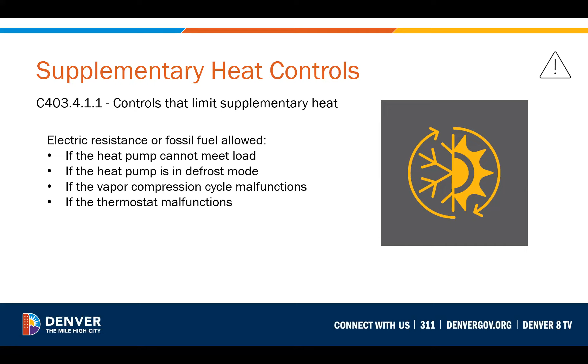Note that there is this supplementary heat controls requirement as well. The point of this requirement is just really to ensure that the heat pump is being used as the primary source of heating in a heat pump system, and that supplementary, or I just refer to it as backup heat, is only being used when the heat pump can't meet load. If there's an issue, like the vapor compression cycle malfunctions, it's in defrost mode, or if there's another issue with the thermostat. So really only in emergency situations, or again, when the heat pump can't meet load, which we talked about is necessary still sometimes on a really cold day that you need that electric resistance supplementary heat.